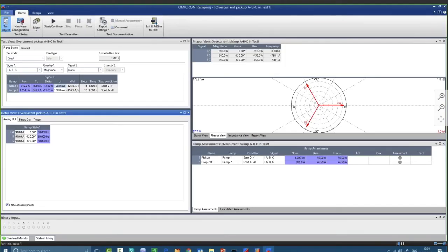That element, for example, inactive, I will make it forward as a direction, or make it non-direction, for example, and the other element, whose stages will be available. Once I exit that one, what I will find is that line differential will be disabled, overcurrent should be enabled.